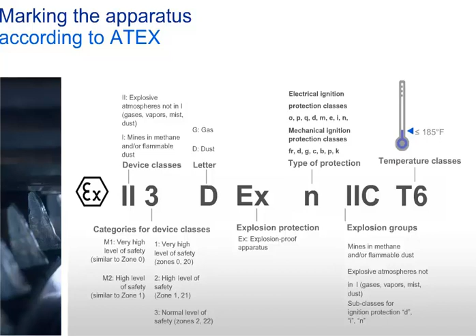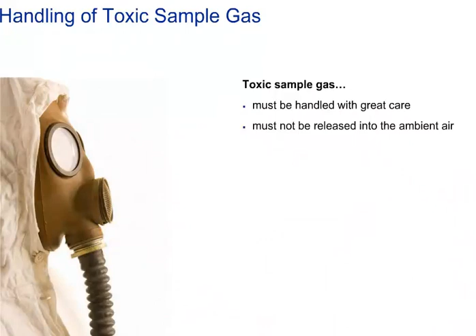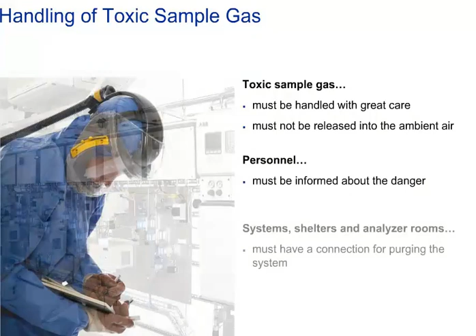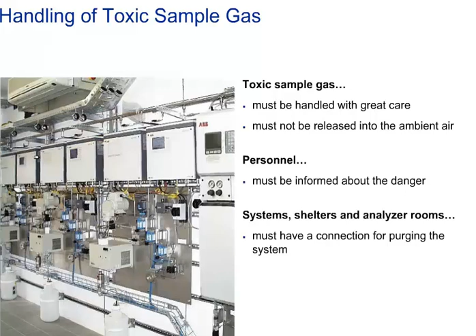Toxic sample gas must also be handled with great care. A sample containing toxic gases must not be released into the ambient air. The personnel dealing with it must be informed of the dangers, and the material safety data sheets of the components in question must be accessible. An analytical system handling toxic gas must have a connection for purging the system with inert gas or air. The system must be purged sufficiently in advance of any maintenance, which includes exchanging parts in the sample gas path, such as valves and filter elements.